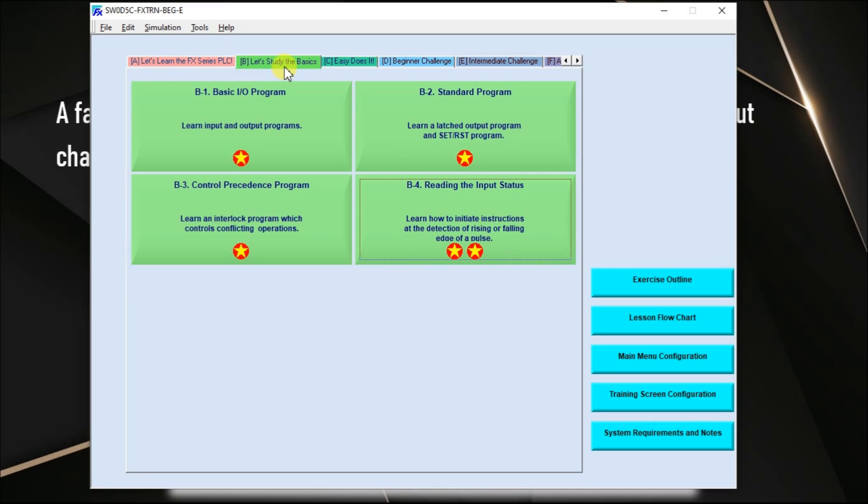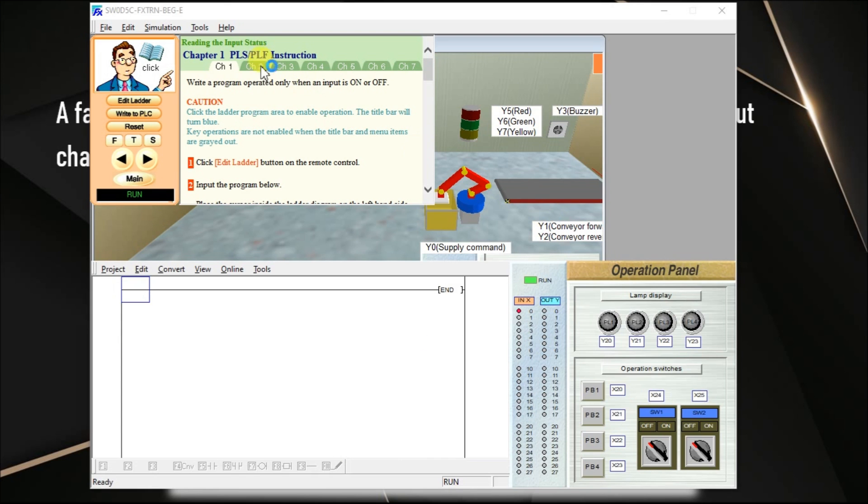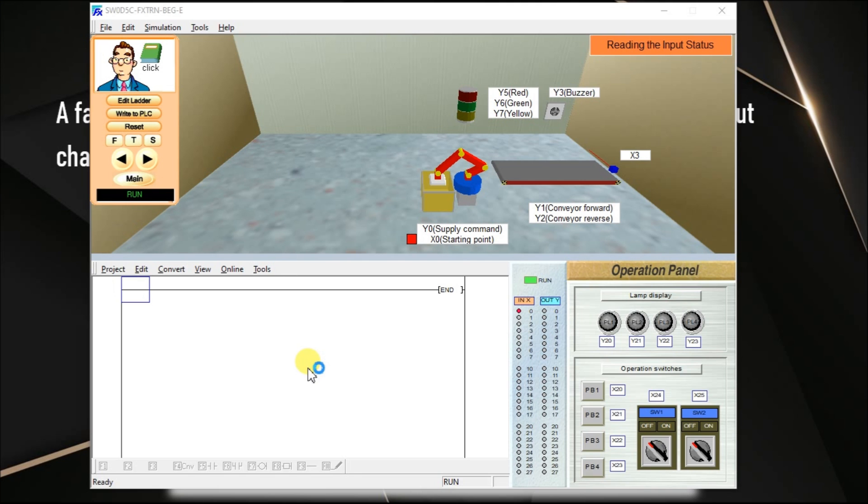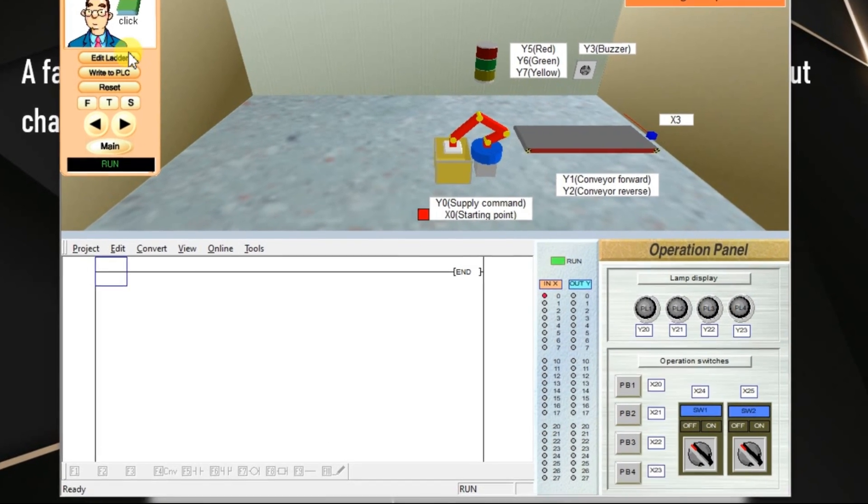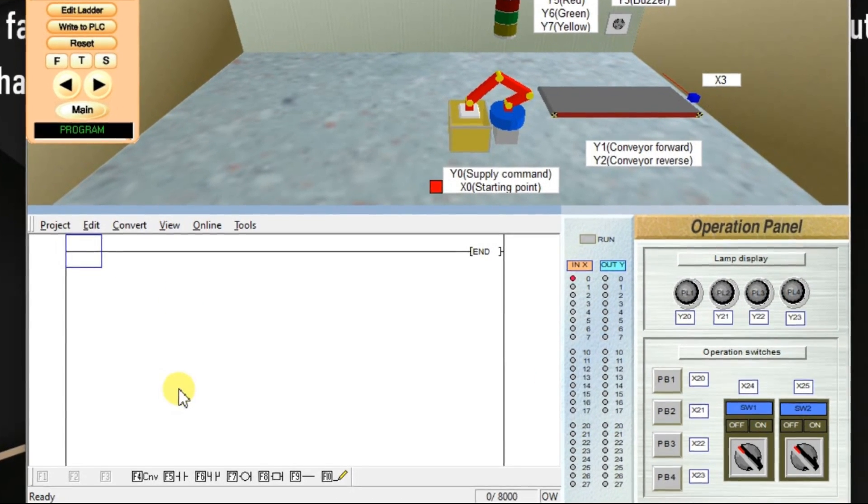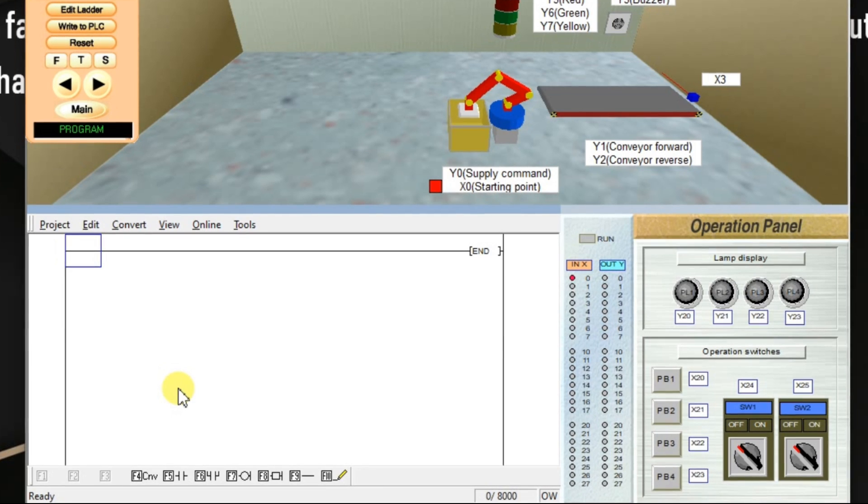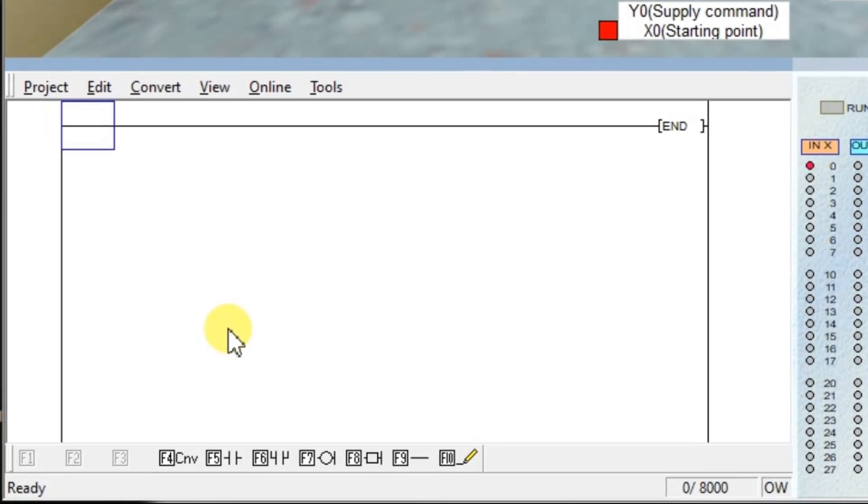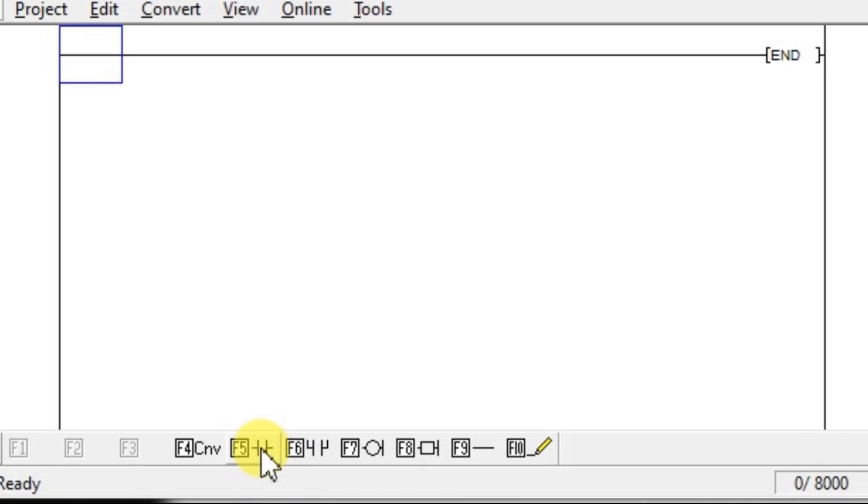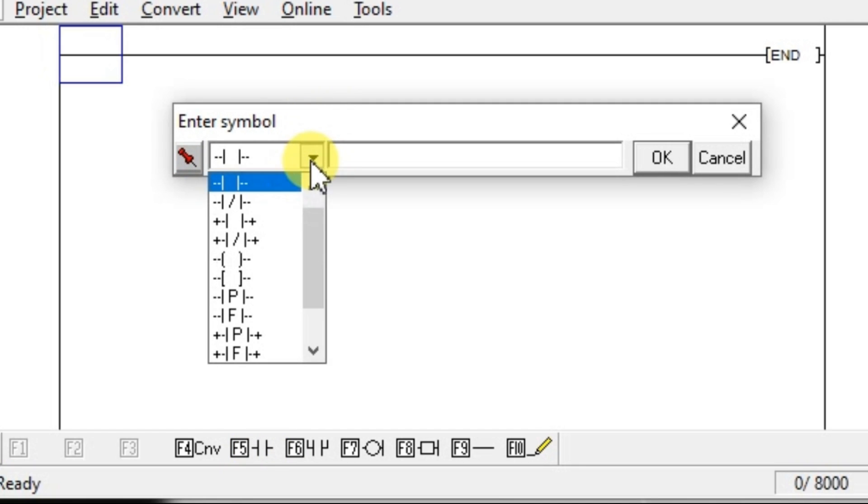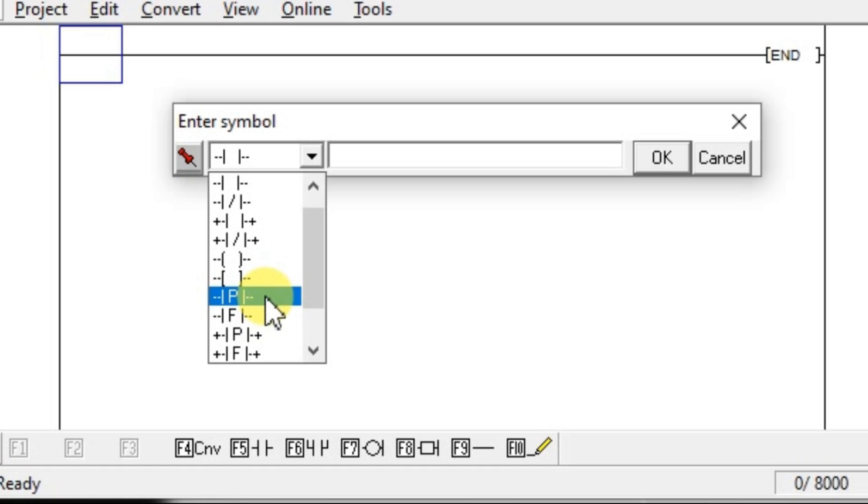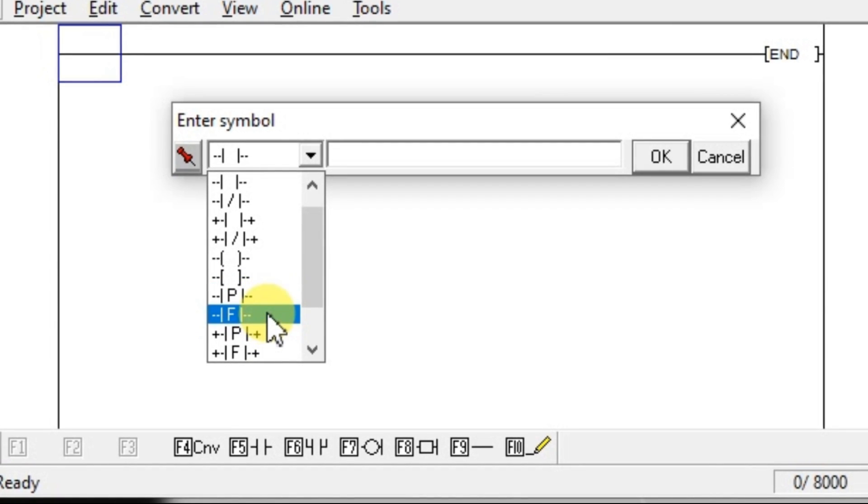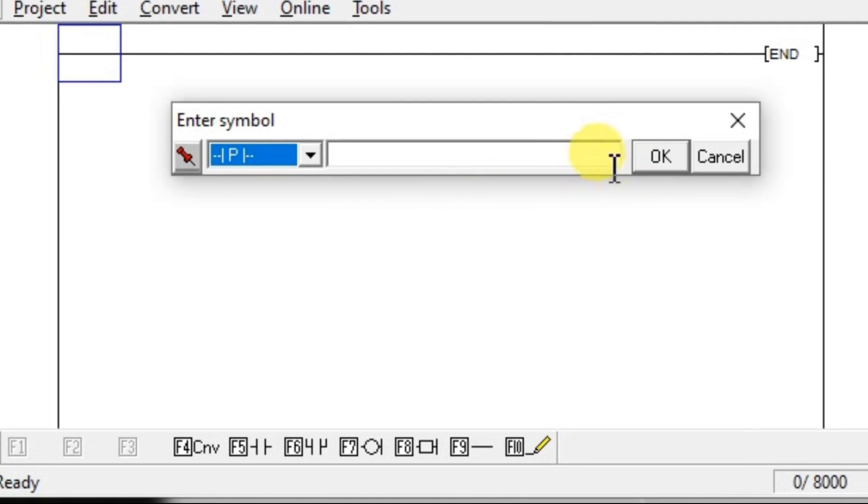Go to category B and B4. Click Edit Ladder and first insert the rising edge instruction. Click on this contact, open the menu drop down. You can see P and F. This P represents rising edge, F represents falling edge. Select P and click OK.